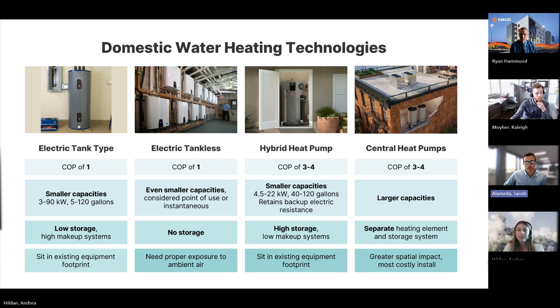There are also opportunities to produce domestic hot water from the building's heating hot water loop in your building. But you need to keep in mind that you need to have a hot enough heating hot water loop to be able to do that. So if you went with a 165-degree heating water system, you can do that, but you're not going to be able to do that as easily if you went down to 130 degrees. And you have to be careful if you do that because it can restrict your setback temperatures on your heating hot water loop. And if there is a desire to eventually drop that 165 heating water down to 130 or something like that, you'll have to figure out a whole new solution for your domestic hot water at that point.